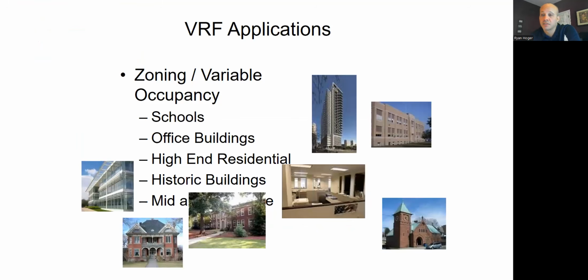Common applications, a lot of it's been retrofit stuff. And most of it's not this high-rise thing. That usually ends up being a chiller boiler job, but it could be. But all these other ones, older building retrofits, old schools and old offices, little churches and banks and stuff like that, even some new construction stuff, those are all good applications for this. Historic buildings especially, because you don't have room to put ductwork in most cases, or they won't let you make the room, right? It's easier to get pipes through a wall than ductwork through a wall. And a lot of those buildings didn't have cooling, and now you're trying to add it. And as an option with that, you end up getting heat pump, right?